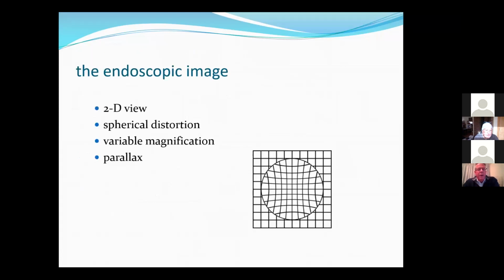The issue with the endoscopic image is that it is actually 2-dimensional. But because you're continually moving the scope within the ear, the subtle changes in the field of view when processed allow you to configure a 3D understanding of the operative field. So it is important that you don't strap the endoscope down or try and work from it from a frame, because you actually rely on those tiny movements of your left hand in which you're holding the endoscope to allow you to form that 3D understanding.